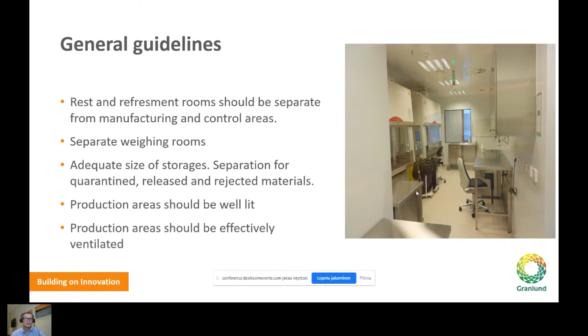Here are some examples of grade D and grade C areas of a clean room hospital pharmacy. Structures in hospital pharmacies are typically designed using sandwich elements. We normally use polyurethane elements coated with galvanized steel, usually 65 millimeters thick or a little more, and this element structure should form a totally airtight shell.